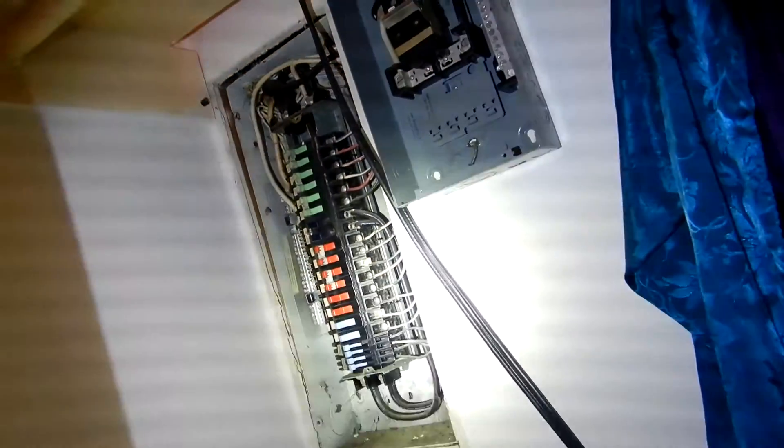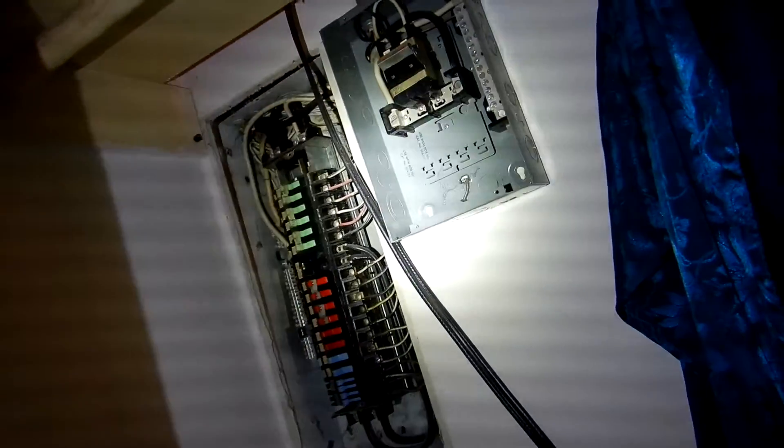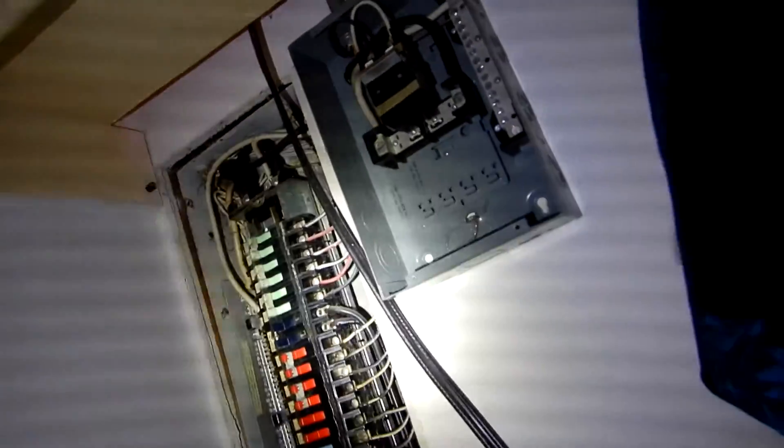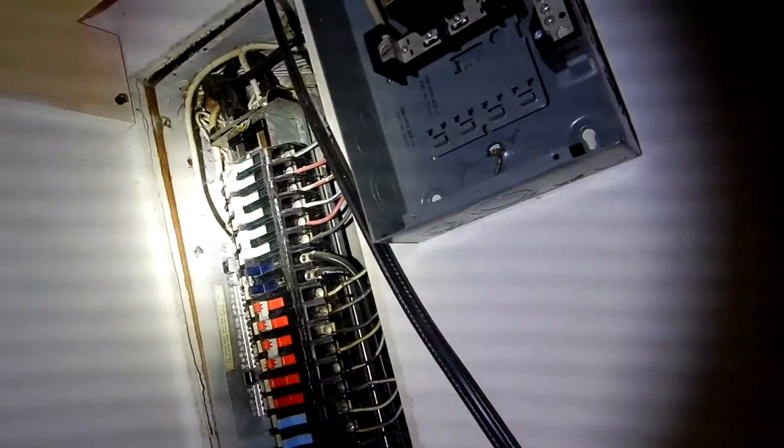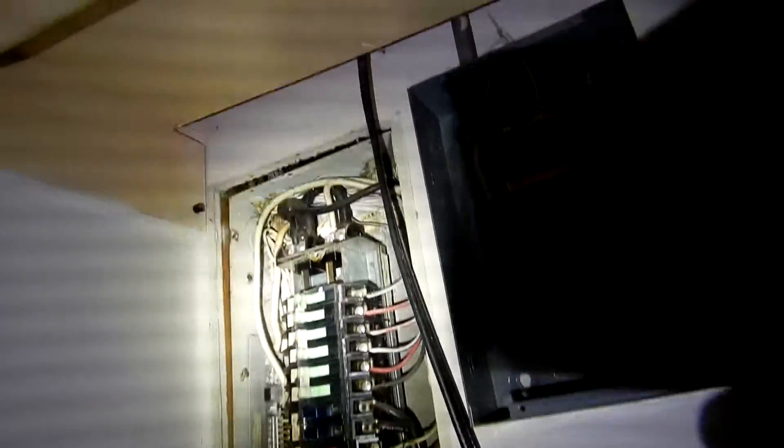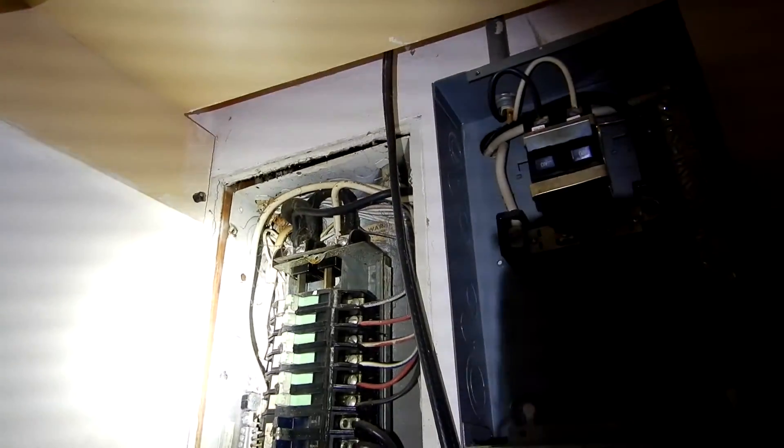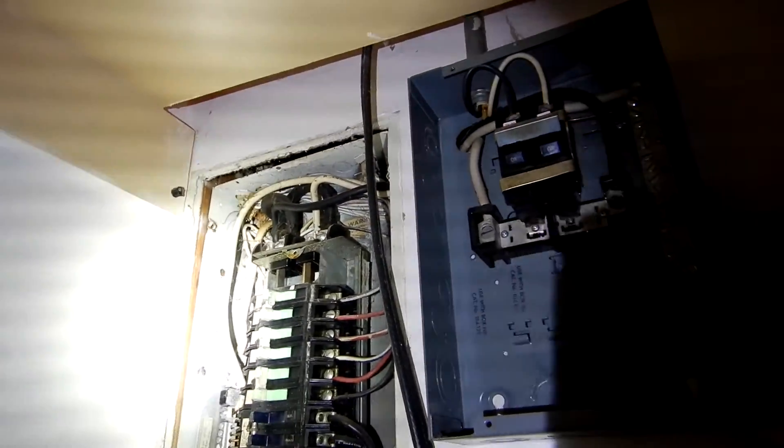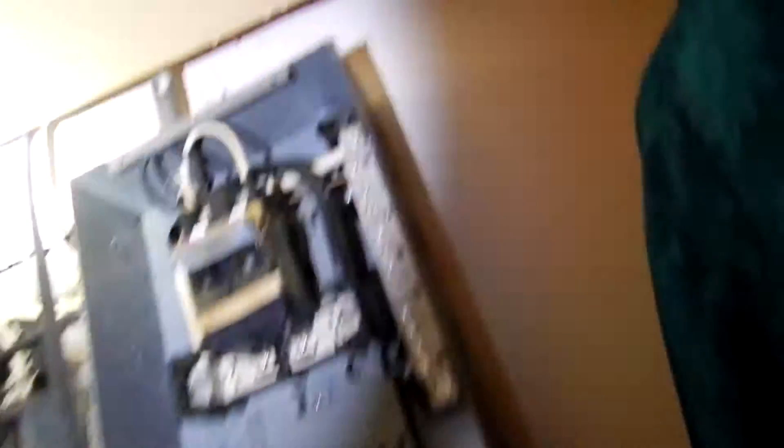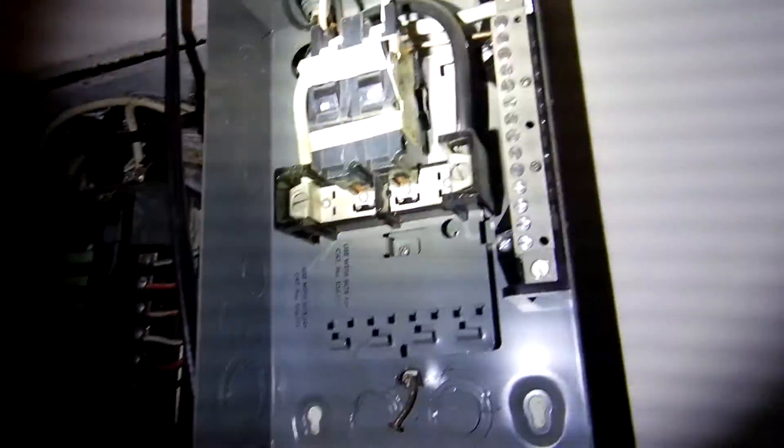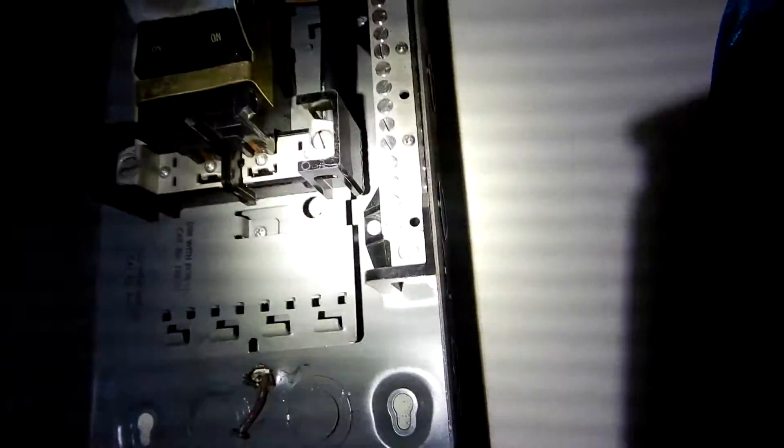We also learned from the roofing video that some of the wires on the service drop cracked - the insulation wires on them. We've got white hots. The second panel, some people call it the sub panel - the ground and neutral are improperly bonded. They're not supposed to be bonded in this panel. They're supposed to be bonded in this panel.